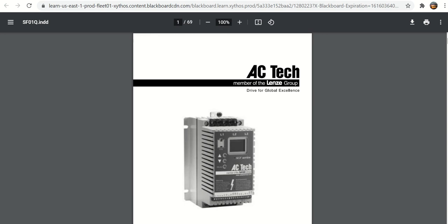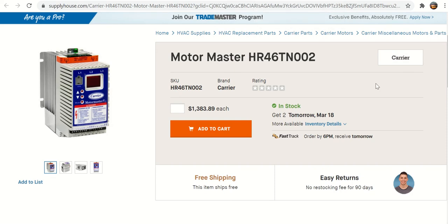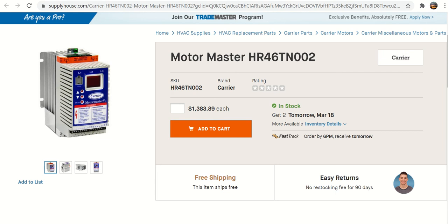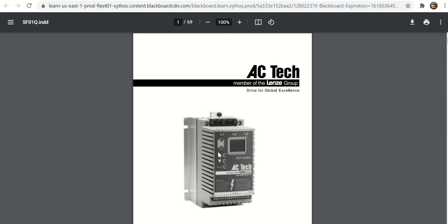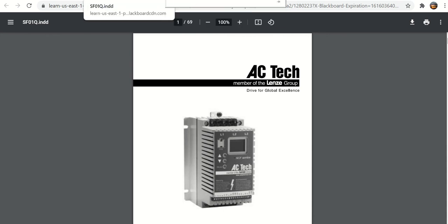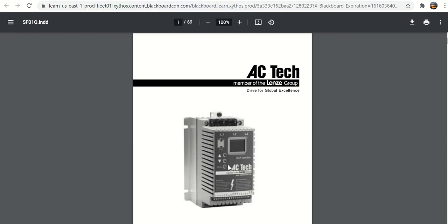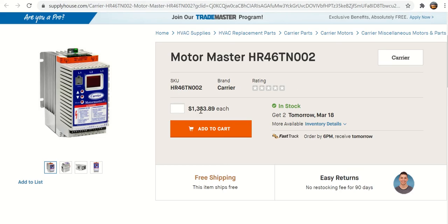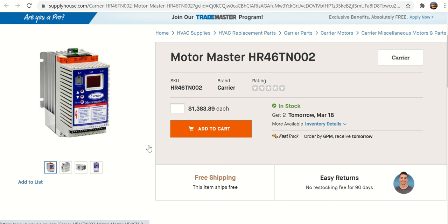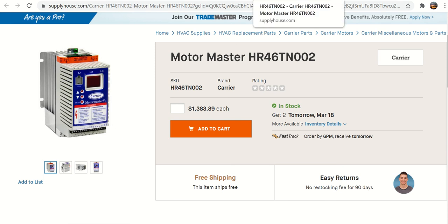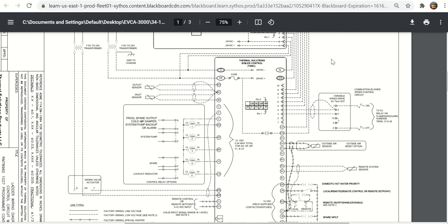If you look at that and you think, well, that looks a lot like the Carrier Motor Master. There's a Carrier Motor Master for condenser fan controls, $1,400 worth of VFD. It's the exact same thing. Carrier buys these from ACTECH and puts their label over top of it so that you would never know that that really is an ACTECH VFD. You could probably buy from the Lenze Group this ACTECH drive online for about half of the price that Carrier charges you for it. Carrier gives you a pressure transducer with it, but that's how they justify charging that much money.